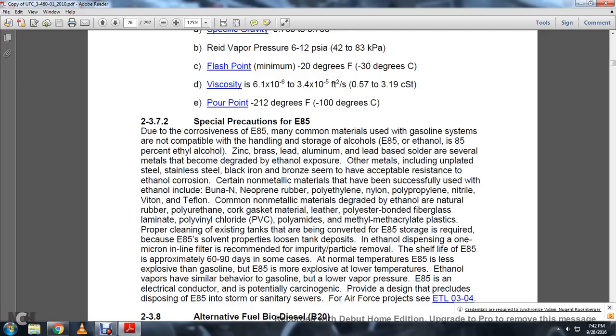Due to the corrosiveness of E85, the common materials used in gasoline systems are not compatible with the handling and storage of alcohols. E85 is 85% ethanol alcohol. Brass, lead, aluminum, and lead-based solder are several metals that become degraded with ethanol exposure. Other materials, including stainless steel, steel, black iron, and bronze, seem to have acceptable resistance to ethanol corrosion. Certain non-metallic materials have been successfully used with ethanol, including Buna, neoprene, rubber, polyethylene, nylon, polypropylene, nitrile, Viton, and Teflon. Common non-metallic materials degraded by ethanol are natural rubber, polyurethane, cork, gasket material, polyester bonded fiberglass laminate, polyvinyl chloride, and polyamides.